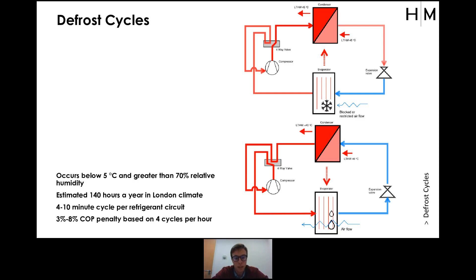So it goes into a cycle of defrost that will heat up that heat exchanger and then rid your heat exchanger of frost. Those penalties can be 4 to 10 minutes per cycle per refrigerant circuit, and that can happen 4 times an hour depending on the conditions.